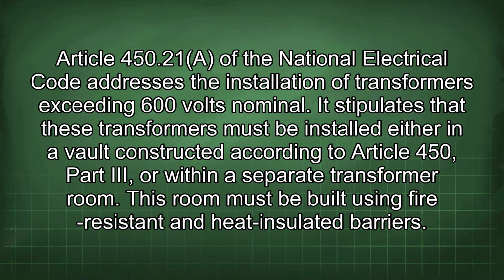450.21 of the National Electrical Code addresses the installation of transformers exceeding 600 volts nominal. It stipulates that these transformers must be installed either in a vault constructed according to Article 450 Part Roman 3 or within a separate transformer room. This room must be built using fire-resistant and heat-insulated barriers.